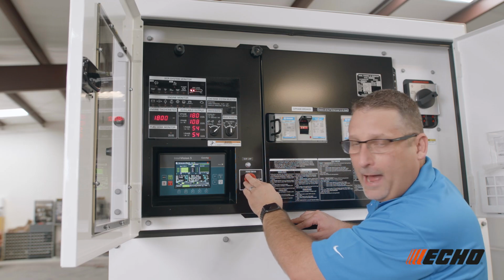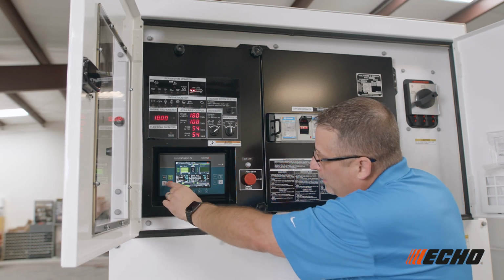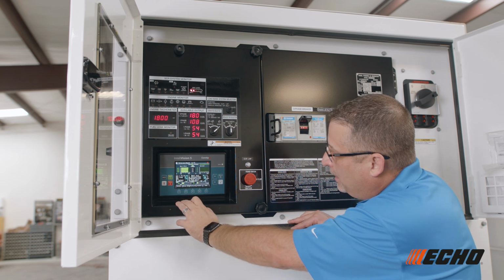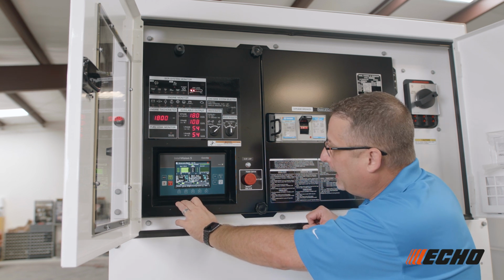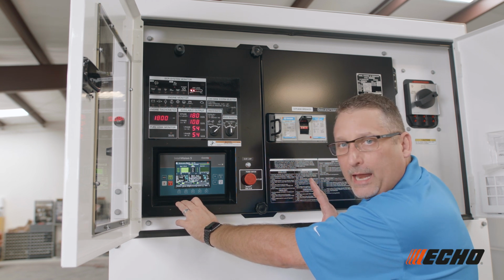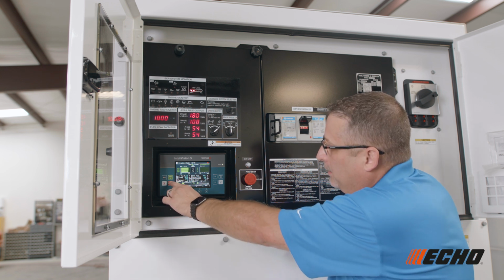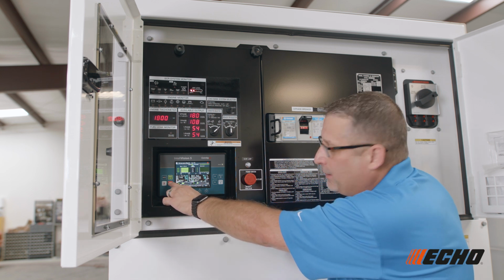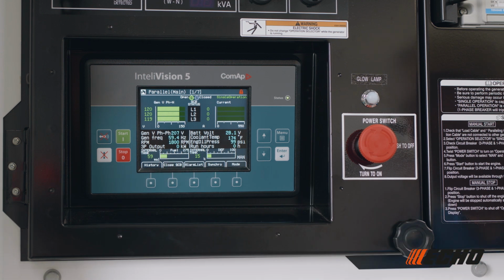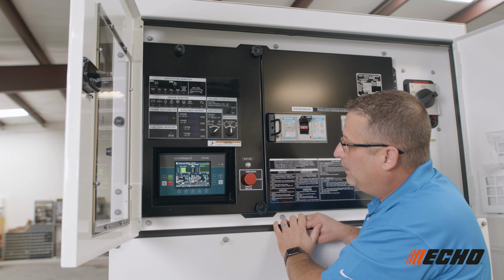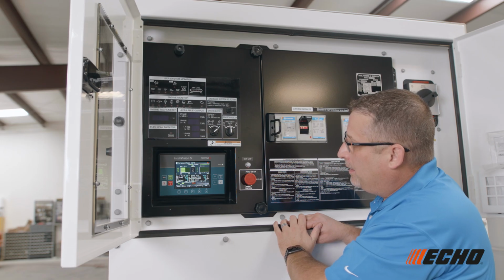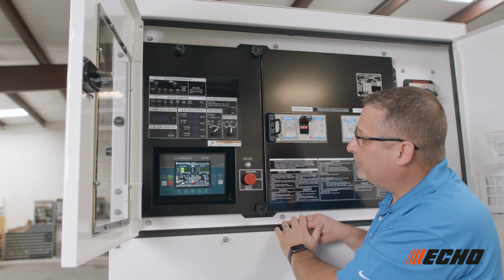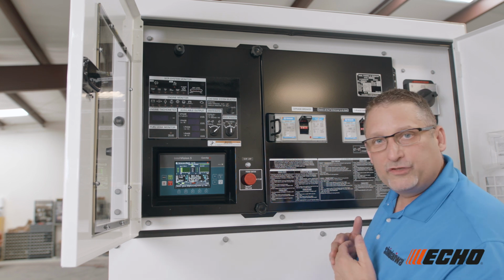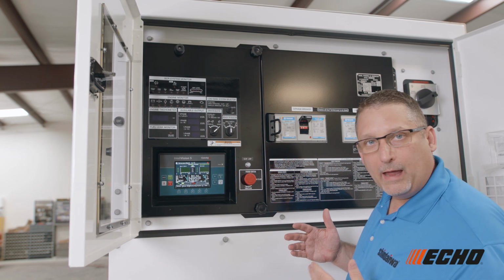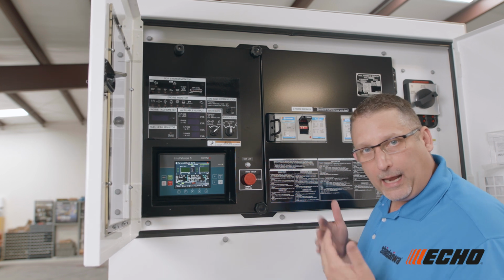Go ahead and shut the machine down. We'll hit the stop switch. Notice the contactor just opened back up. You're on a time delay to cool at this point. If you want to bypass that time delay, you hit the stop again. That's the basic functionality of the single unit operation, where you'll have simul-phase available to you as well. So you'll have three-phase, single-phase, and a combination thereof.